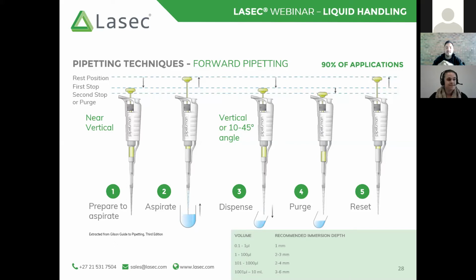And just in the bottom right of the screen, you will see recommended immersion depths. This is quite important for accuracy. As you can imagine, if you submerge a tip too deeply in a solution, what's going to end up happening is you're going to have that sample gathering on the outside of the tip. This means that if you do then dispense that tip, you risk having whatever's on the outside of the tip also being dispensed with that sample. And you can obviously imagine that affects the accuracy and the precision. So these are just terms that are always going to come up because that was the goal of using a pipette. So although these are recommended immersion depths, I wouldn't expect anyone to measure in their pipetting cycle how far they are immersing that tip.